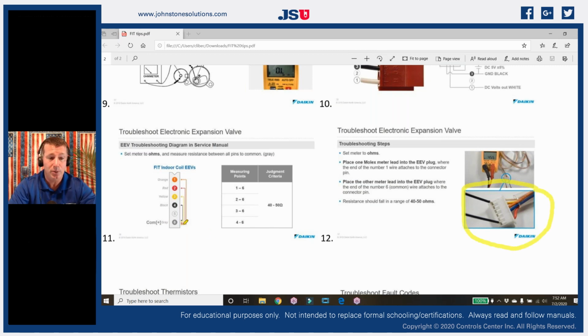And we make sure that we put common out there on its own so that everyone knows that it is common and it's away from the rest of the wires. So we leave a blank one in between them. So there's common. So we're simply going to check from common to coil number 4, common to coil number 3, common to coil number 2, and common to coil number 1. And all 4 of those should be identical. You should have the exact same resistance between each one of those.